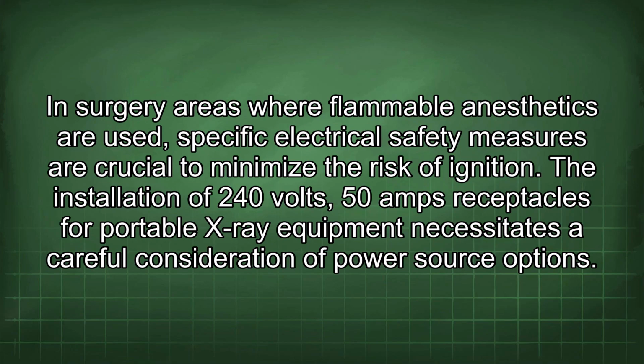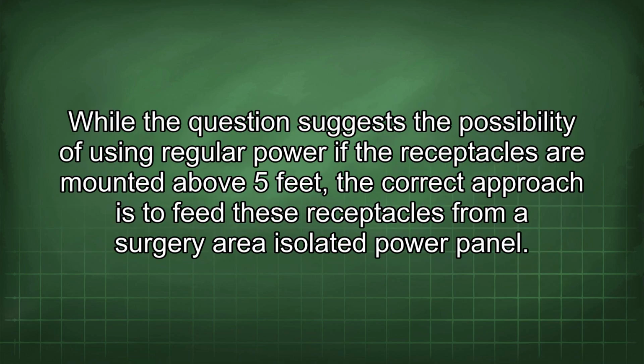In surgery areas where flammable anesthetics are used, specific electrical safety measures are crucial to minimize the risk of ignition. The installation of 240 volts, 50 amps receptacles for portable X-ray equipment necessitates a careful consideration of power source options. While the question suggests the possibility of using regular power if the receptacles are mounted above 5 feet, the correct approach is to feed these receptacles from a surgery area isolated power panel.